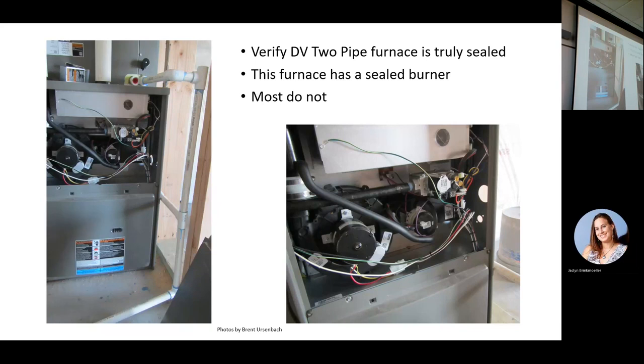Now, I want to say a little bit about direct vent furnaces. I don't know about you guys, whether you are HVAC contractors or competitors, but we sure see a lot of them in the Wasatch Front that only want to run one pipe on their 95% efficient furnaces. They run combustion air in for a bigger combustion air, obviously a bigger pipe size for the code, which doesn't make any sense to me, because I think it's easier to run a small 2 or 3 inch PVC than it is to run a 7 or 8 inch pipe and put a grill and everything on it. But it's a much better system because then it's direct vent. If you do not run both pipes, it is not direct vent and it doesn't fit the definition of direct vent in other parts of the code. So we have to run both pipes to call it sealed.